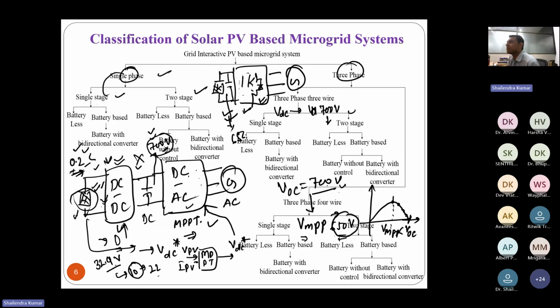Now, can we have 650 volts here? If I have 650 volts, what will happen? I'll not get 415 volts at the converter output. And if I'm not getting 415 volts at the converter output, my per unit voltage goes beyond the 0.88 to 1.1 per unit range required for successful synchronization with the grid. If it's not within that limit, and it further reduces beyond it, say to 350 or 300 volts, my converter output will not be synchronized with the grid.